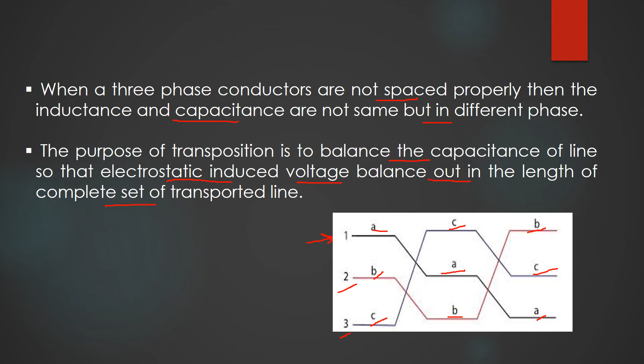If we talk about cables, then the swapping of the position of the two conductors is gradual and continuous. That is, the two or three conductors are twisted around each other, and that is how the swapping of the conductors takes place in cables. For communication cables, this is called a twisted pair. Whereas in the case of overhead power lines, the conductors are exchanged at the transposition towers or at the utility poles.